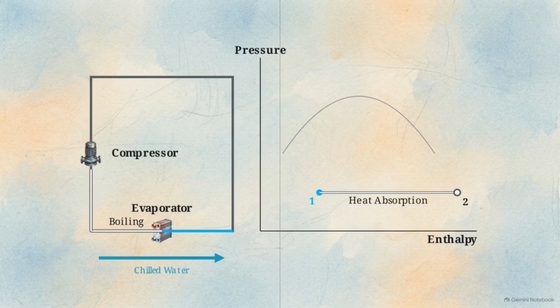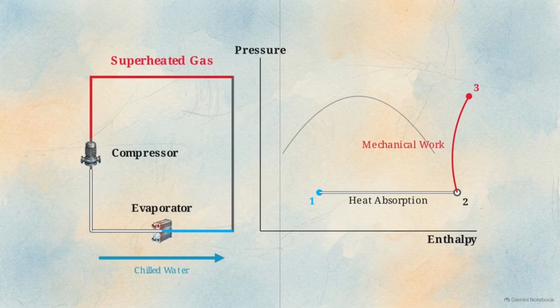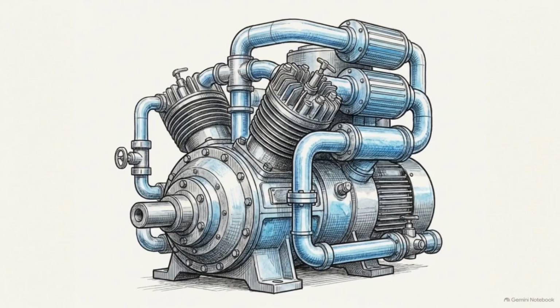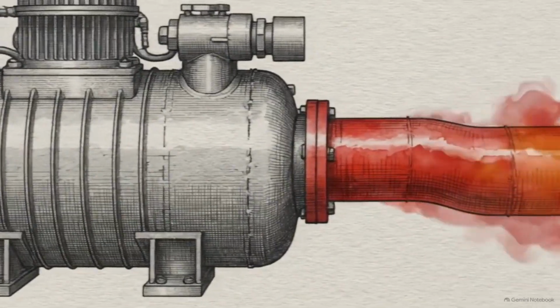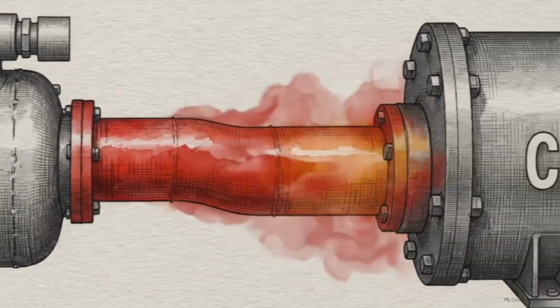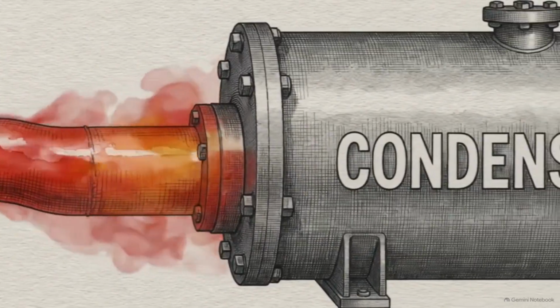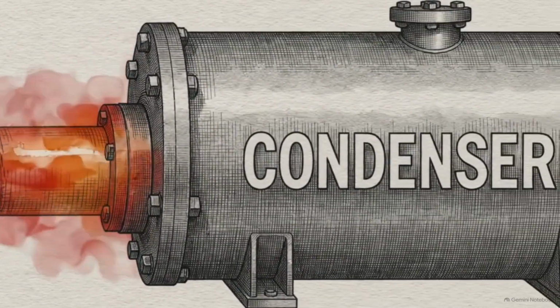That low-pressure vapor enters the compressor. Acting as the system's mechanical heart, it forcefully packs the vapor, drastically increasing pressure and temperature. This work appears on the chart as a sharp, curved rise. The refrigerant is now a highly pressurized, superheated gas. The scale of the building's heat dictates the machinery used here. Small to medium loads use scroll or reciprocating compressors, but heavy industrial applications rely on massive centrifugal compressors to handle high-volume flow. This brings us to the third node in the loop, the condenser.